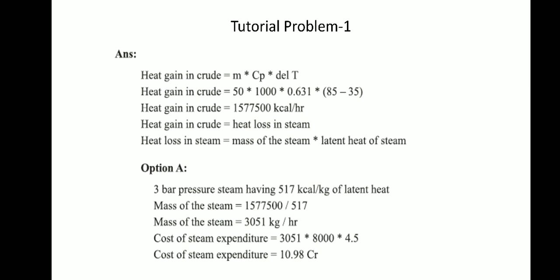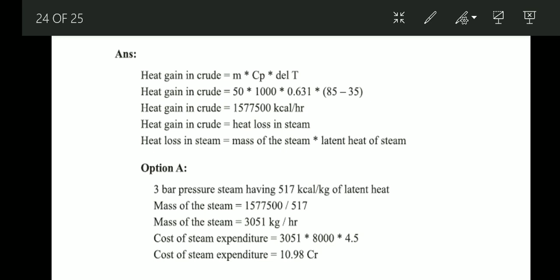Then option A, which is 3 bar pressure steam. The 3 bar pressure steam has 517 kilocalories per kg of latent heat. Then the mass of steam is 3051 kg per hour. Then the cost of the expenditure is 10.98 crores. In option B, 8 bar pressure steam has 489 kilocalories per kg, which is lesser than 3 bar pressure, because as pressure increases, the latent heat of evaporation reduces. Refer to the PH diagram or TS diagram or any property diagrams of pure substances. Then the mass of steam required is 3225 kilograms per hour, which is a higher amount than 3 bar pressure steam. Therefore, the cost is 11.61 crores.